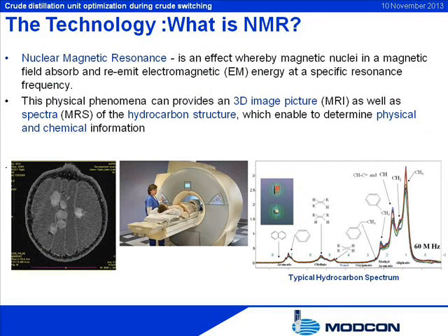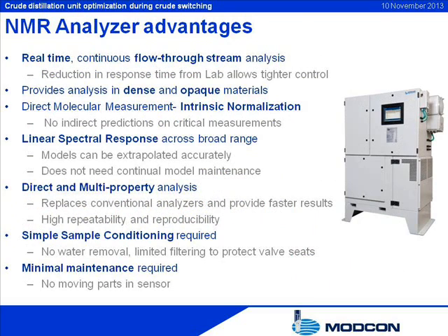Nuclear magnetic resonance is an effect whereby magnetic nuclei in a magnetic field absorb and re-emit electromagnetic energy at a specific resonance frequency. This physical phenomenon can provide a 3D image picture as well as a spectra of the hydrocarbon structure, which enables determination of physical and chemical information. NMR technology advantages include: real-time continuous flow-through stream analysis, analysis in dense and opaque materials, direct molecular measurement, intrinsic normalization, linear spectral response across a broad range, direct and multi-property analysis, simple sample conditioning required, and minimal maintenance required.